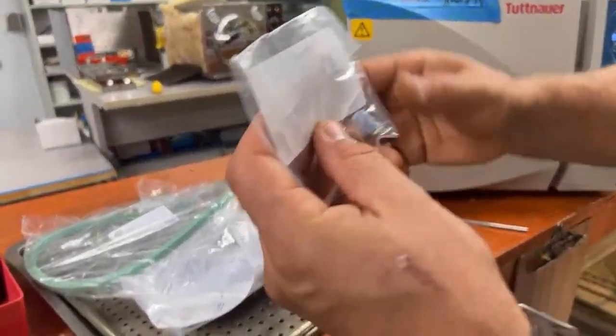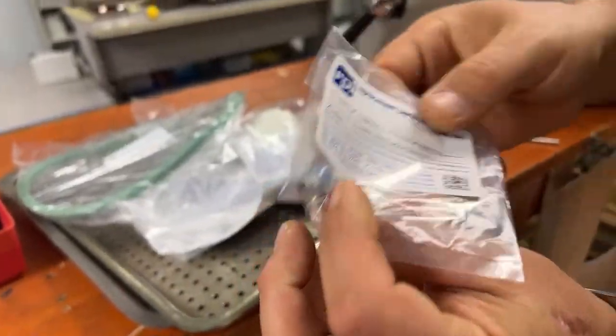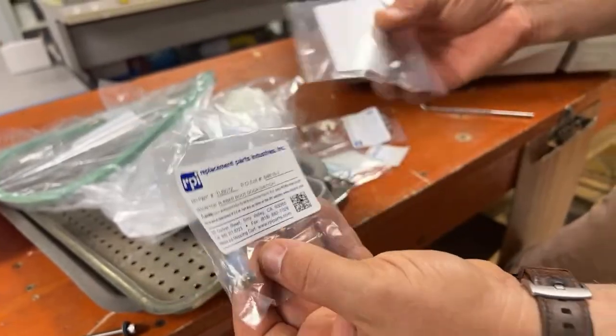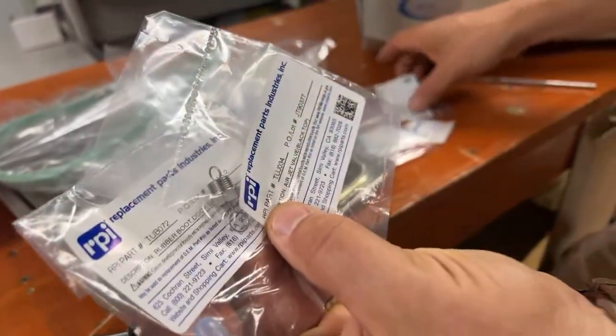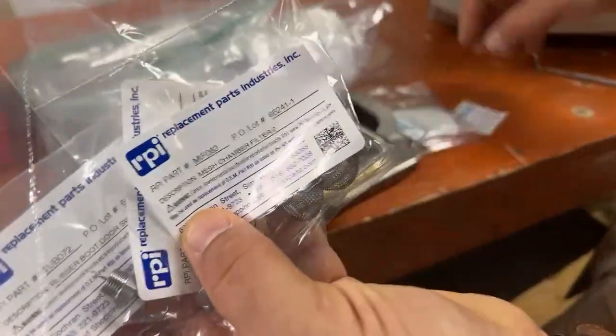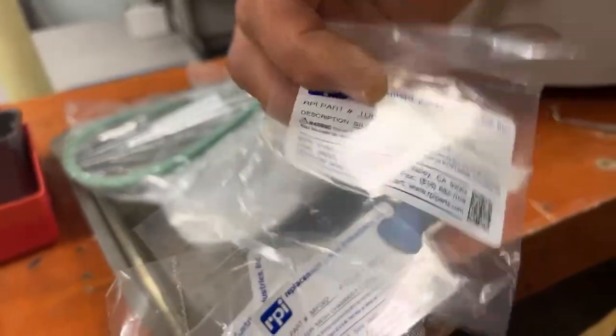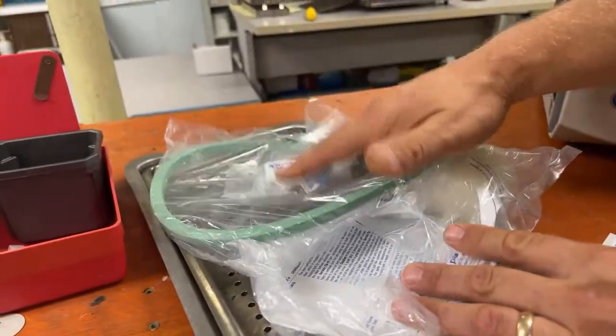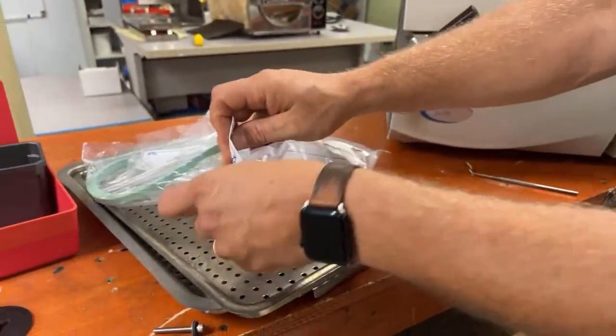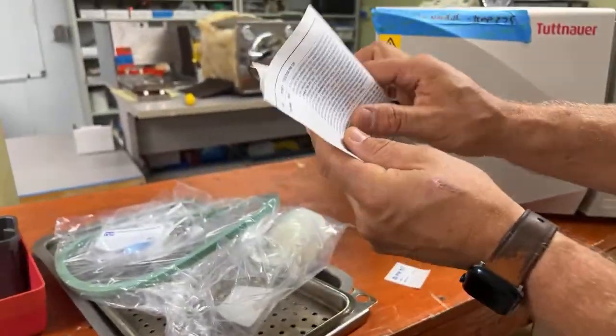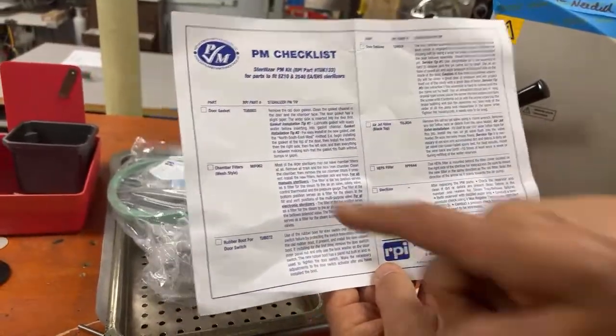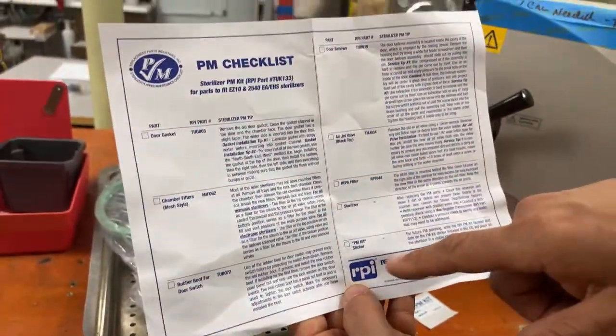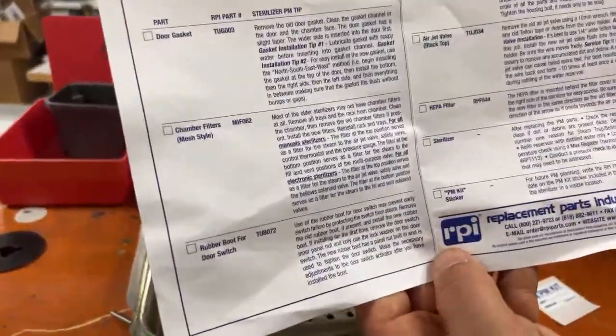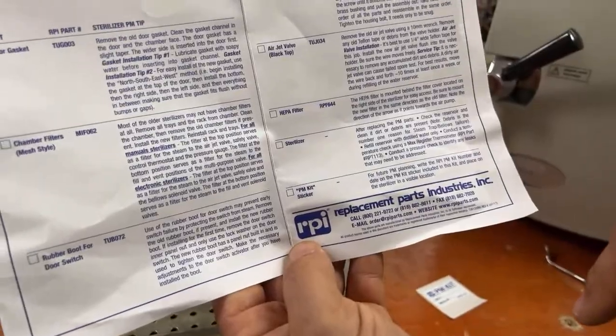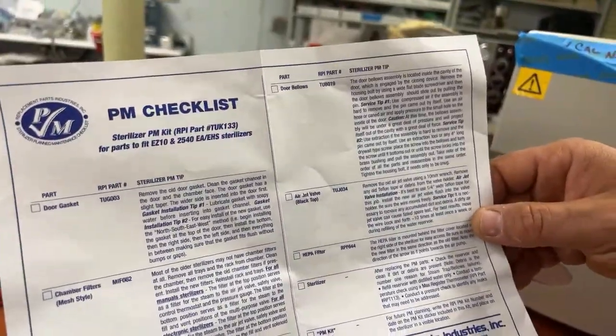All right. So right here, there's a little door safety switch cover that goes on the door safety switch. Here's our air jet. That's what that looks like. There are some chamber mesh filters, and there's also this bellows that's inside the door. And then there's a HEPA filter right here, and then there's the gasket. The other thing that's nice, for those of you starting to do these PMs, is that the PM checklist RPI gives us is great. They tell you exactly what to do in the right order, and it even tells you how to do those different things. So this is a great checklist, and RPI has a lot of really quality training information.